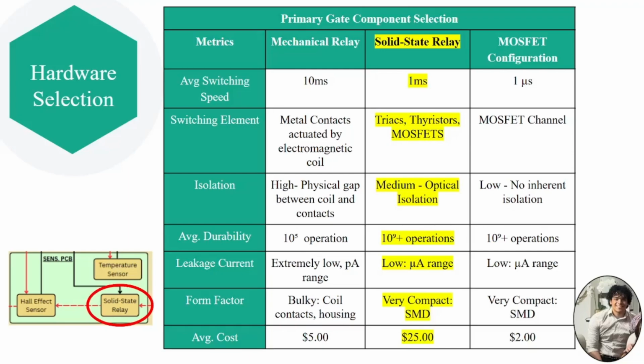The first specification we wanted to look at was average switching speed. The NFPA and IEEE don't specify a switching speed for conventional breakers used nowadays, so we decided 10 milliseconds should be the absolute slowest, since that's typically how fast a normal breaker works.